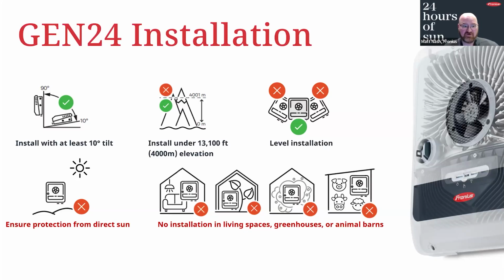So these are the requirements for installation. If you're going to install it, you need to have it at either a 90-degree or 10-degree tilt. The reason you can't lay it flat is because of the fan in the center. The 10-degree tilt will allow water to shed off the fan, so that it doesn't just get flooded. Install it under 13,000 feet. Make sure it's a level installation. You don't want it cattywampus.